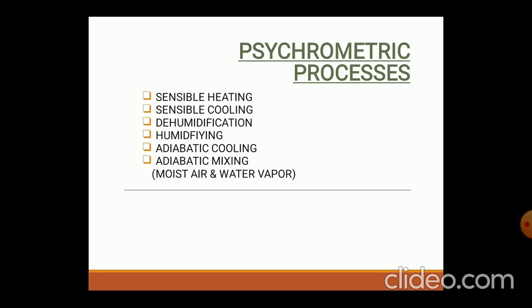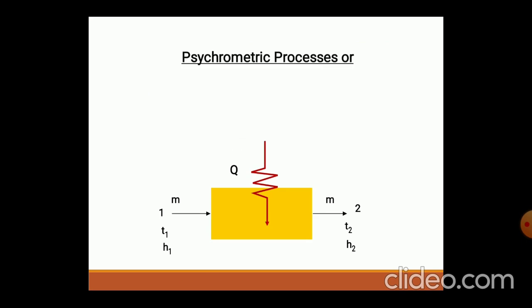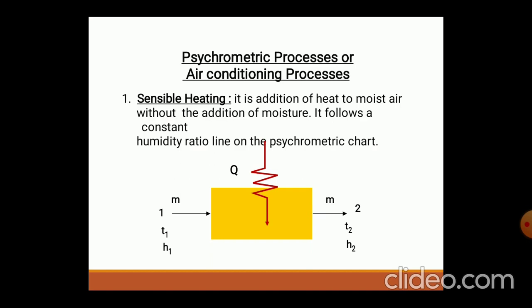The first psychrometric process is sensible heating. What is sensible heating? It is nothing but the addition of heat to the moist air without the addition of moisture. There is no moisture content — only heating. Such type of heating we call sensible heating. On the humidity ratio lines of the psychrometric chart, we can see this process on the sensible heating line.